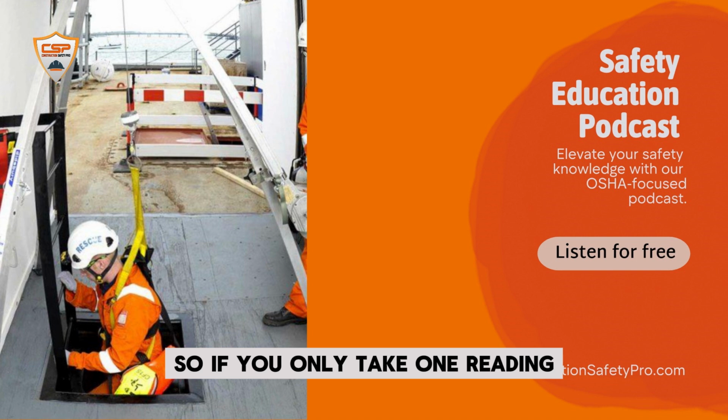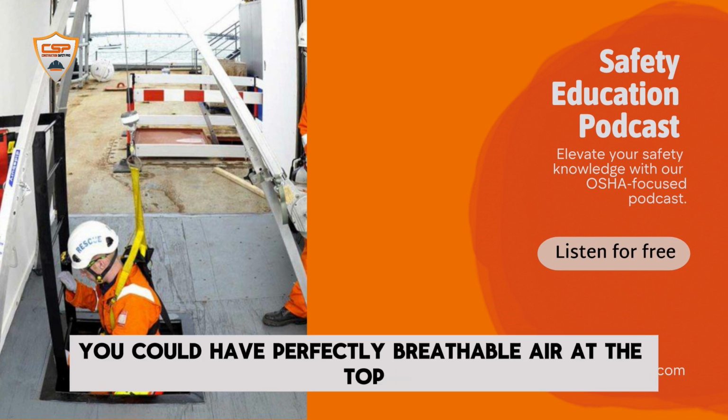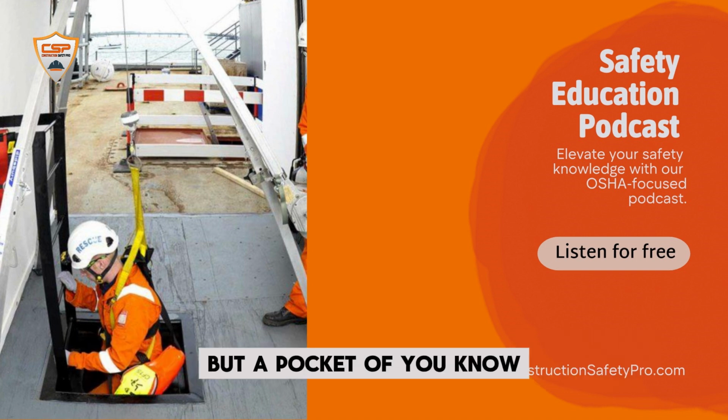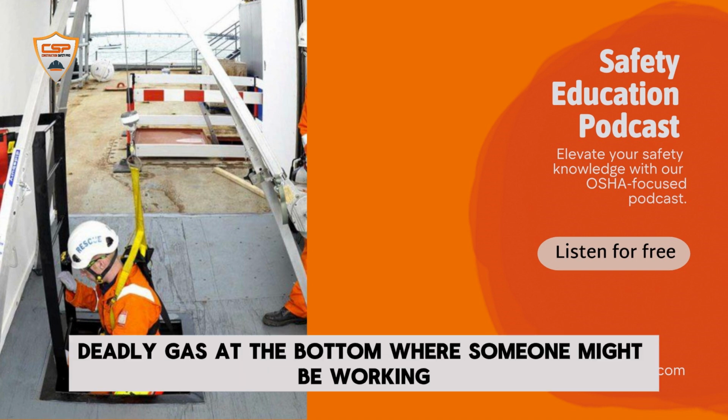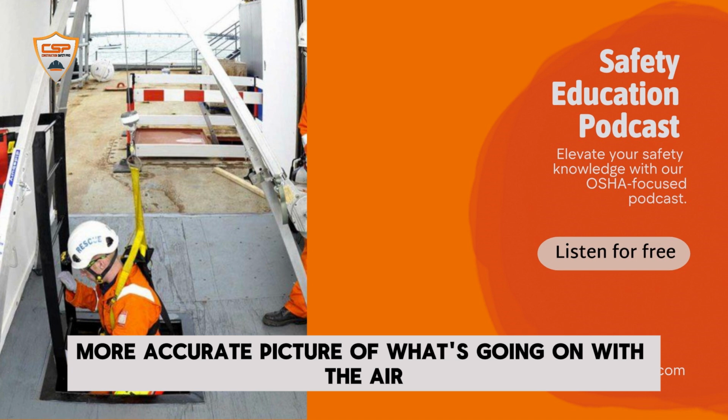So if you only take one reading, you might think everything's fine when it's not. Totally. You could have perfectly breathable air at the top, but a pocket of deadly gas at the bottom where someone might be working. Exactly.